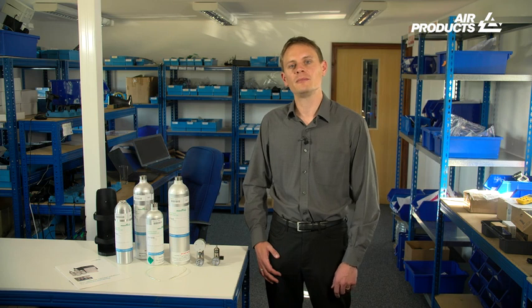A common method of testing gas detectors in the field is by using a pressurised canister of test gas, and its quality is crucial to reliable and accurate gas detection. Let's look at some characteristics of a gas mixture that affect its suitability. A supplier providing a calibration certificate is likely to be a more reliable source. This document includes information about the measured concentration of components in the mixture, how the measurements were made, and how accurate they are.